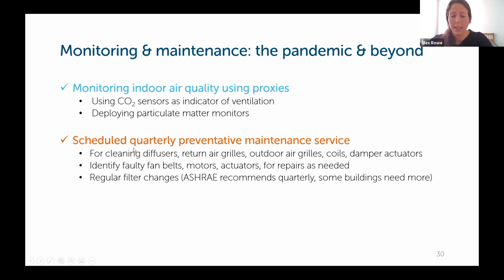In addition, they revamped their ongoing preventative maintenance schedule, where they're cleaning equipment, diffusers, and return air grilles more frequently, identifying any faulty fan belts, motors, and actuators on an ongoing basis, and then increasing those filter changes. ASHRAE recommends quarterly, but some buildings will need more than that. But that's what this customer chose to do.